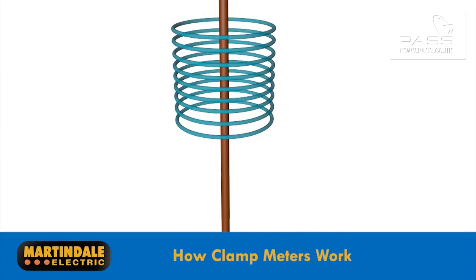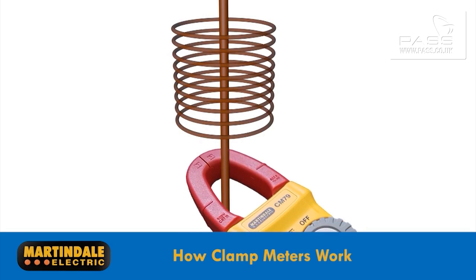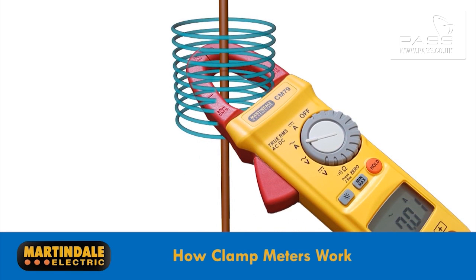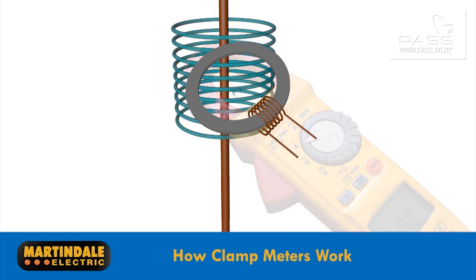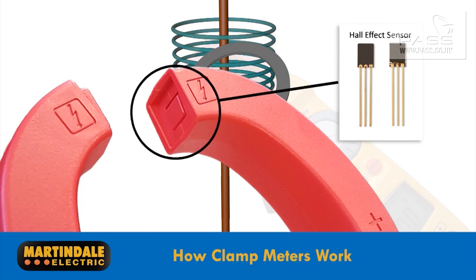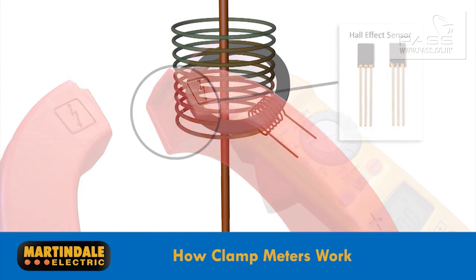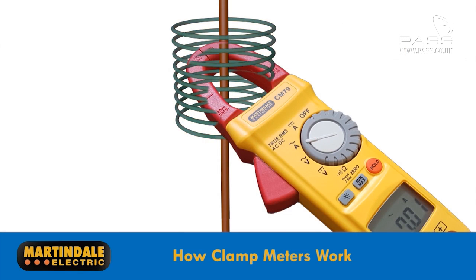Essentially, they all measure the magnetic field generated by the current flowing through the conductor. The jaw of the clamp forms a magnetic circuit around the conductor, and the magnetic field is measured through a current transformer wound around the jaw for AC currents, or a Hall effect sensor built into the jaw for DC currents. The clamp meter then does the clever stuff and displays the actual value of current flowing in the conductor.